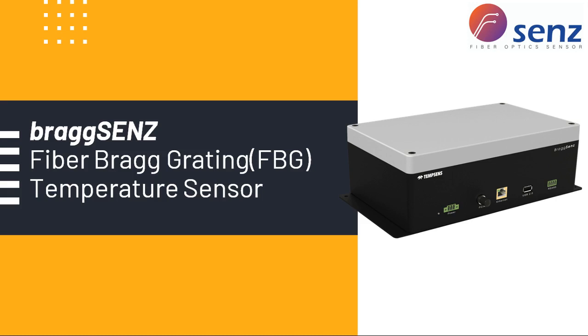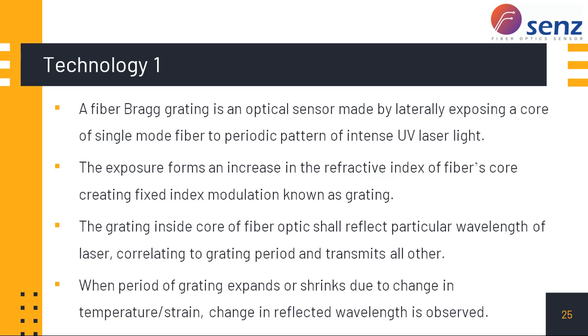The next one is based on fiber Bragg grating. We have named this product braggSENZ. It measures temperature, but the same technology can also be used for measuring strain for any object. A fiber Bragg grating is made when the fiber is exposed to intensive UV light, and this writes the grating on the fiber. Like this, the grating is fixed at that particular point, and we can write multiple gratings on a fiber. Each grating represents a particular wavelength, so the gap between the gratings defines the wavelength.